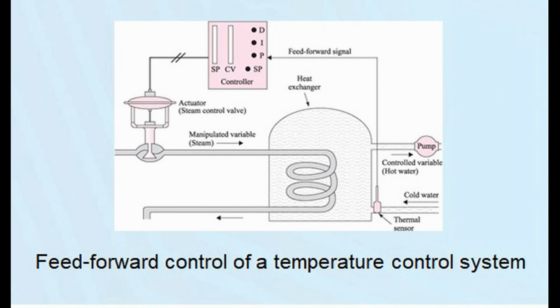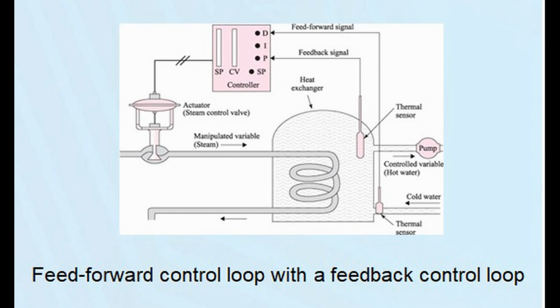In feed-forward control, an attempt is made to anticipate an error. In this case, a measurement is taken of the water before it comes into the tank. The idea is to begin the heating procedure sooner. Most of the time, feed forward and feedback are used together, with the idea of speeding up a procedure that could take many hours or even days. In this case, maybe the tank is so huge that we need to speed up the procedure to save many, many hours of work.